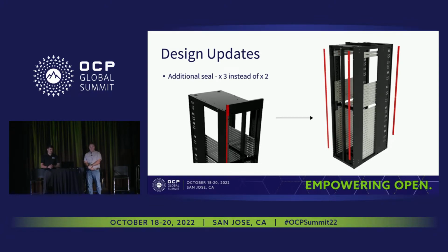Here we've got the side seals used for airflow containment. Originally there were two diagonally across from each other on the frame, as highlighted in red. We've added a third seal. This allows for when these racks are bayed in a data center - if they're not bayed rack to rack, where you have the diagonal airflow block, sometimes they're bayed next to a containment panel. When bayed next to that containment panel, they need this additional seal to make sure you get the airflow block you need. This was one of the most recent updates we did on the rack.